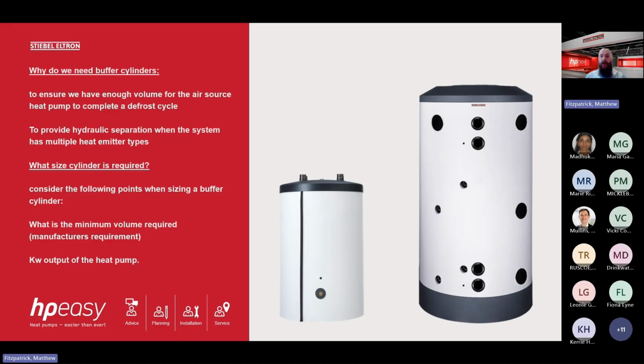So that buffer cylinder provides us with a protective layer of not only volume, but a minimum temperature of around 18 degrees to ensure that if the heat pump has been off overnight and the first run cycle is domestic hot water, it requires a lot of energy from the air. It may potentially need to defrost, but there is a thermal store or mass of energy that the heat pump can use to complete a defrost cycle rather than going into a fault.